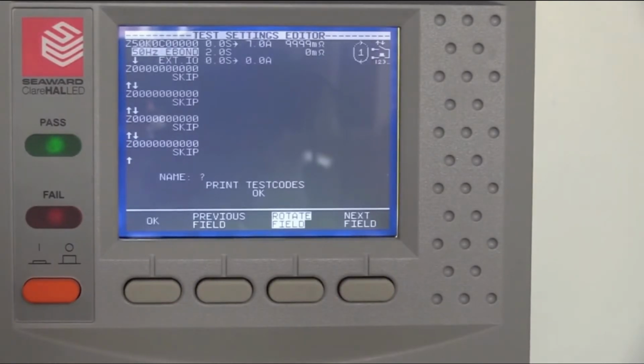So things such as ramp times, hold times, outputs, whether that's current or voltage, depending on the test you're going to perform, limits, if you have any limits you want to set, the number of times you want to perform the test, and also how you want to start the test. So there are a number of different ways we can start any single test within a test sequence.